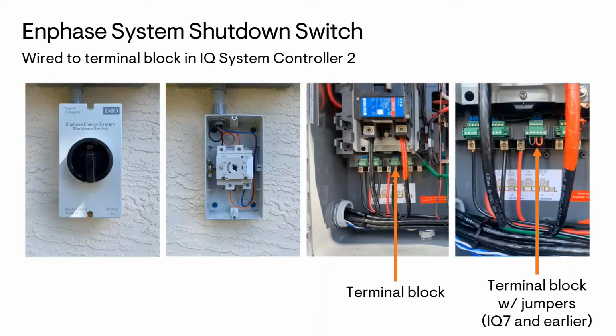I guess one more technical detail for you guys to note. For an IQ8 to actually go from grid interactive mode to grid forming mode, it has to be commissioned with a System Controller 2. It's actually the software process of commissioning that will enable grid forming functionality for the IQ8. So if they aren't installed with a System Controller 2, or for example, if the System Controller 2 fails, the IQ8s are going to default back to regular old grid interactive mode.